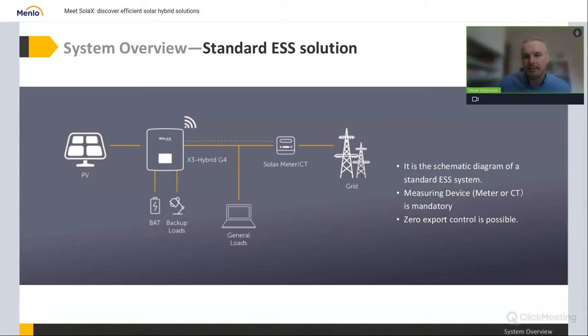System overview of a standard ESS solution. It looks like this: grid, meter, SolaX meter or SolaX CT, and general loads. There's a hybrid inverter with batteries connected, and also backup loads, critical loads connected directly to the inverter, because that inverter uses its internal EPS switch, and of course the PV panels.